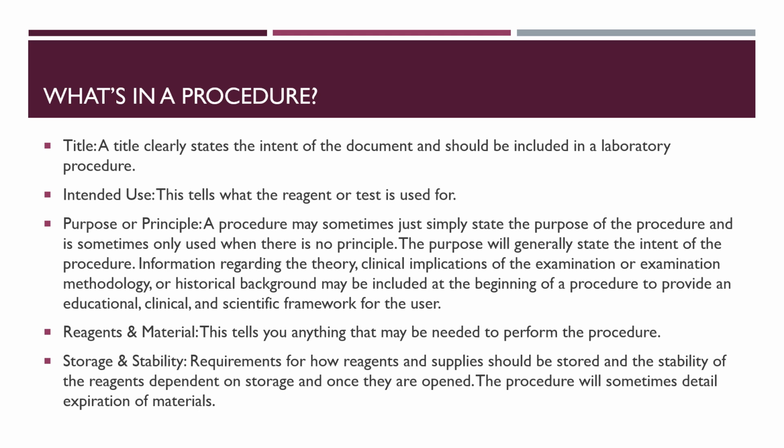Storage and stability. This would be storage and stability of the kit itself, or the reagents, or the samples. It should tell you in detail how long a reagent is good for. When does it expire? Does it expire after 30 days once it's open? These are things the procedure itself would tell you in order to modify the expiration date, or whether a kit is to be stored at room temperature, or maybe it's something that's kept refrigerated, but then you bring it out to room temperature, and once it's at room temperature, it's only good for 10 days.